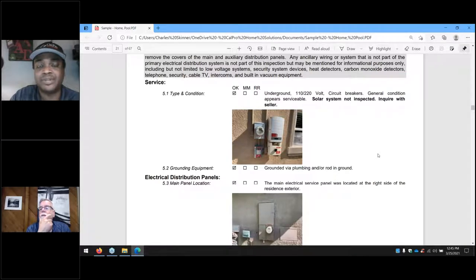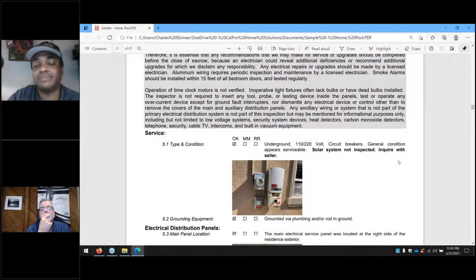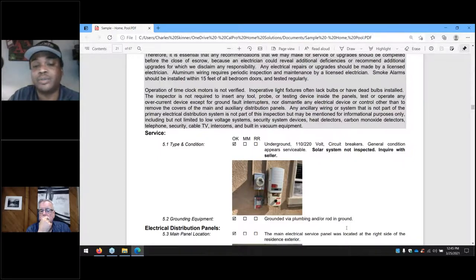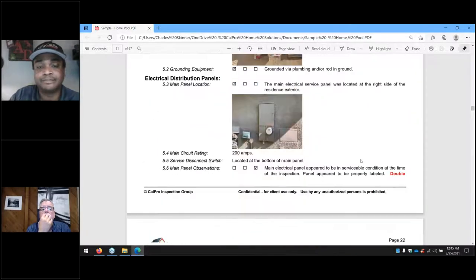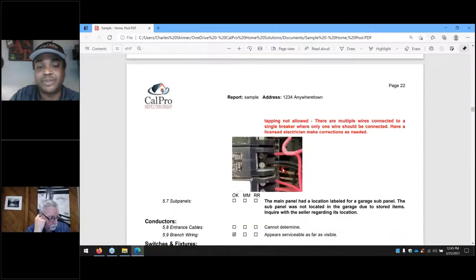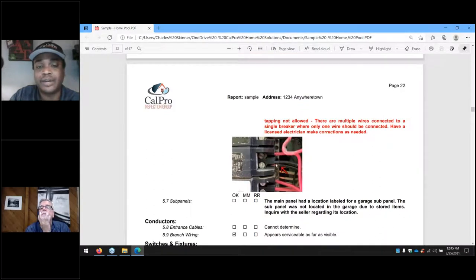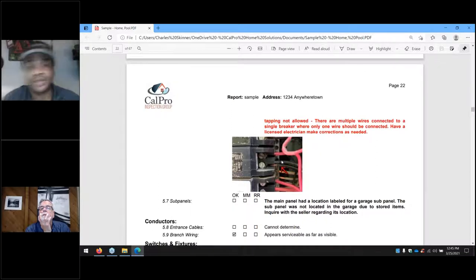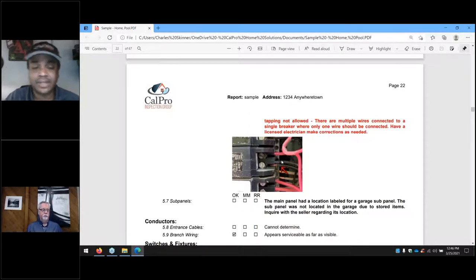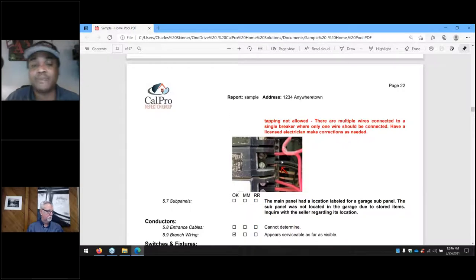This particular home did not have a solar inspection done, but we do offer standalone solar system inspections if needed. In our normal home inspection, solar is not within the scope. When we look at electrical panels, we'll open the panel and look for items like double-tapped breakers — two wires under one lug — which is not proper for any installation. If we see any evidence of arcing or issues with the electrical panel and improper wiring, most of those items will be covered in our normal inspection.